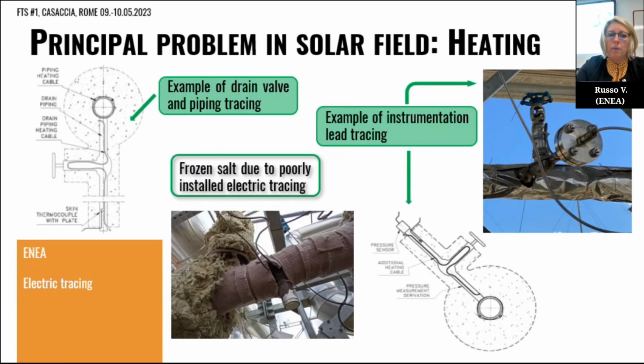Another example of installation tracing is the draining valve. The vent, the drain, all the valves in general are critical components on a CSP plant. In this case, like in the vent valve, the draining piping must be traced for the same reason, because if it is traced for all the length, it permits an emergency drainage of the solar field at any moment.